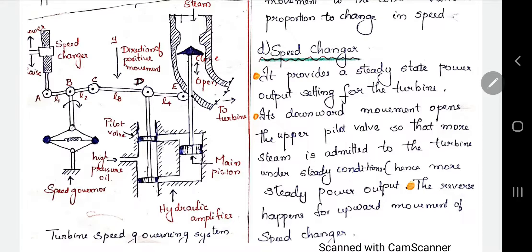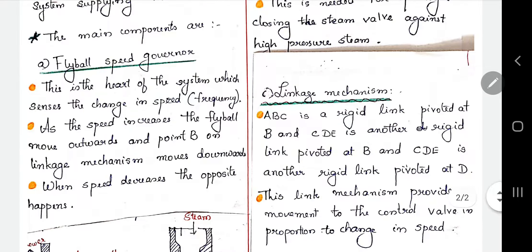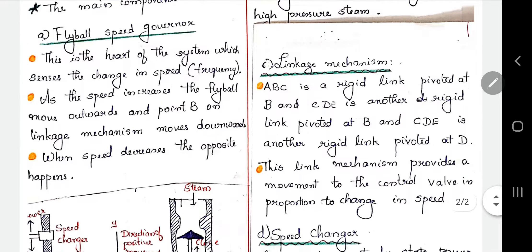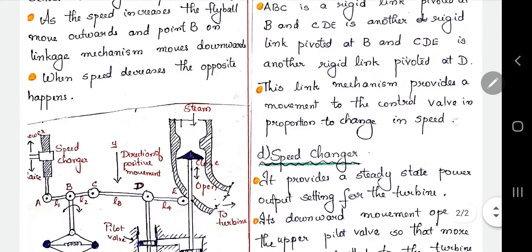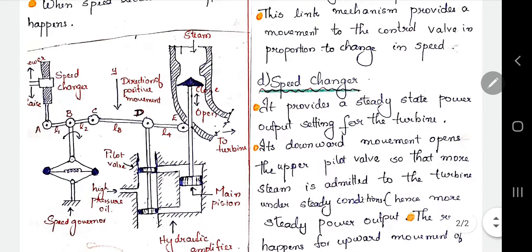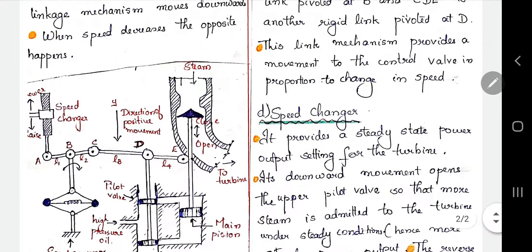The flyball speed governor is the heart of the system, which senses the change in speed. Whenever there is any change in speed, it is detected by the flyball speed governor. As the speed increases, the flyballs move outwards and point B on the linkage mechanism moves downwards. When speed increases, this starts to rotate — these are the two flyballs — and due to this rotation, this linkage mechanism link goes downwards, meaning B moves downward. This is how it starts to control the system.